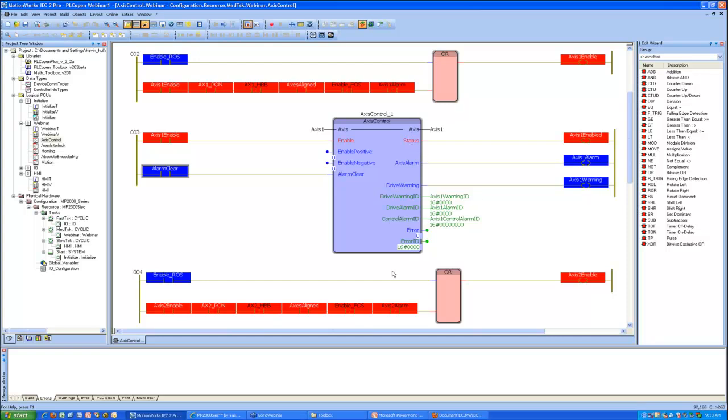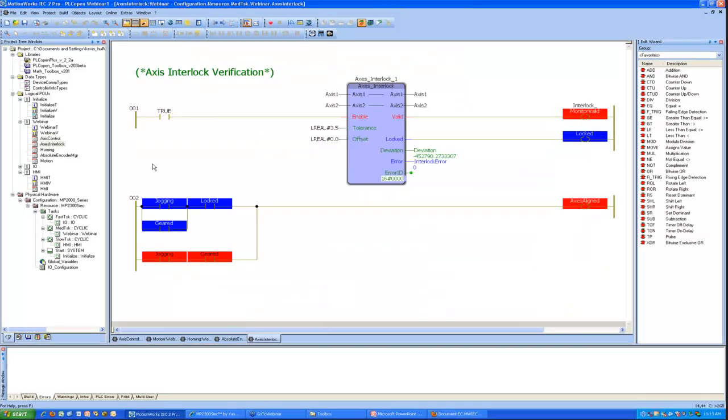It's a three-in-one block that allows you to enable and clear alarms in one system with Y reset Mechatrolink. So we have plans to add another function block called Y reboot controller, which would be a more appropriate name for a function describing the behavior that one would have on the MP2600. And that would basically allow you to accomplish a very similar sequence as we just showed here to clear the amplifier alarms that need power cycle. With the additional caveat that the controller itself is also resetting. So there would be some slight difference in performance or in behavior there.